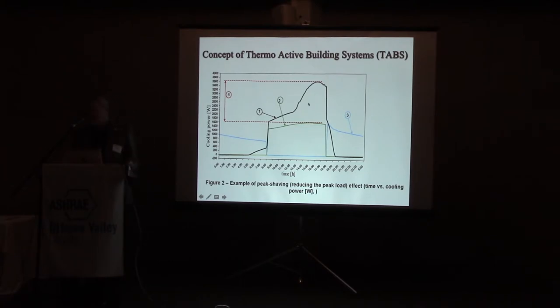And what you see now, the peaks are much smaller. So you can design your system with smaller peak values, which are important, first of all, for the load of the whole system, also on the grid, but it's also important for sizing your equipment. So that's the idea of having a thermal mass where you can store some of the heat during the day and then you can cool it down during night time.